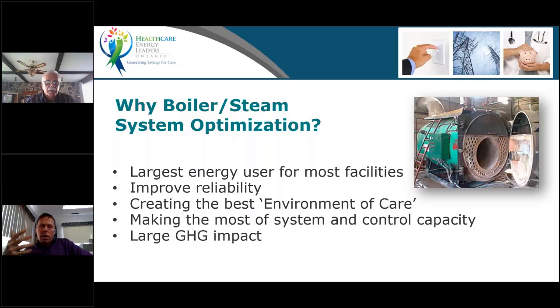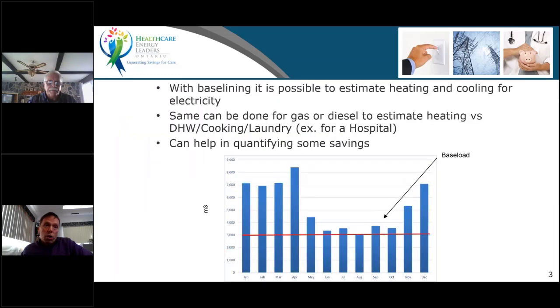And one very distinctive characteristic in a hospital, for example, is the large base load. You do use those boilers all year round. You have needs for reheat, you have need for steam, for sterilization, for dryers, for the kitchen. So it is used all year round, and actually I'm pretty sure in most hospitals, depending on where you're located, it will be the largest GHG impact for your facility, because it's natural gas.